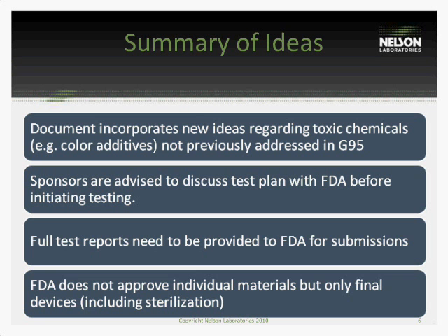Now, there's two ways to do this. The first way we've seen requests from the FDA is to actually perform a leachable study where we mimic the clinical use of the device and actually look for specific colorants that are coming off and then address those amounts. The second way is to limit the leachable study, and we just say this is the total amount of that colorant in the device.